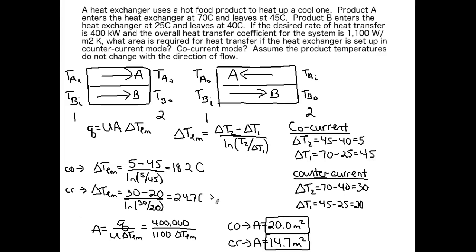So if you're running for weeks, months, years, however long, it's going to save you quite a bit in energy. So by setting your heat exchanger up in counter current mode, that truly is more efficient because you have a higher log mean temperature difference. You are getting your heat transfer accomplished more quickly.